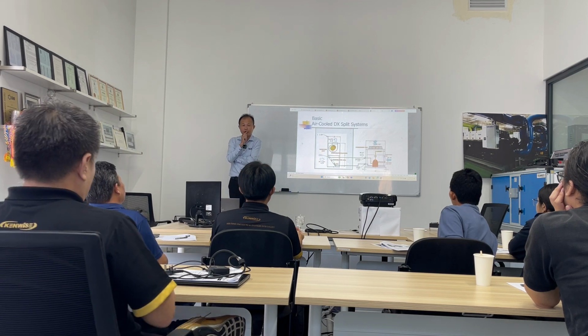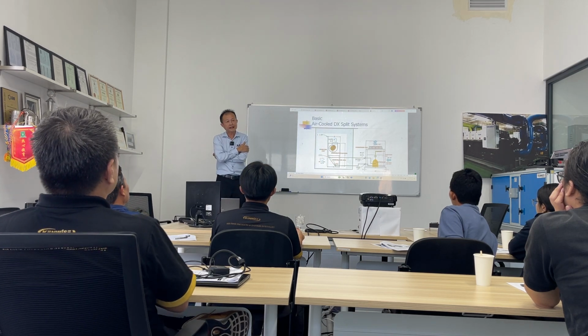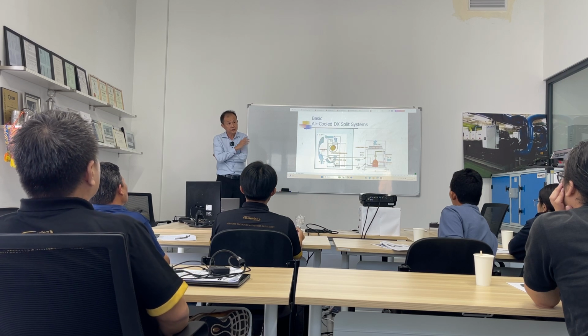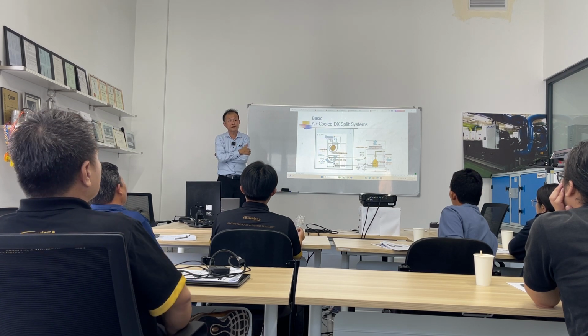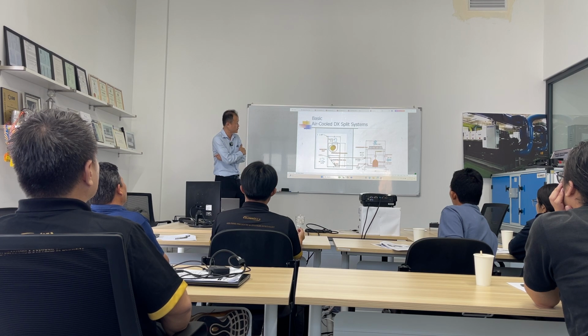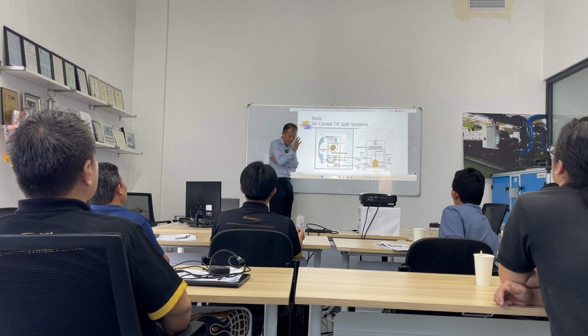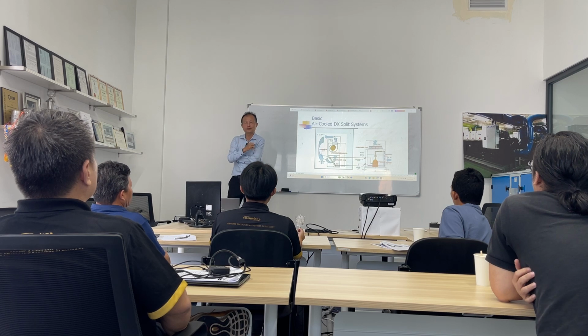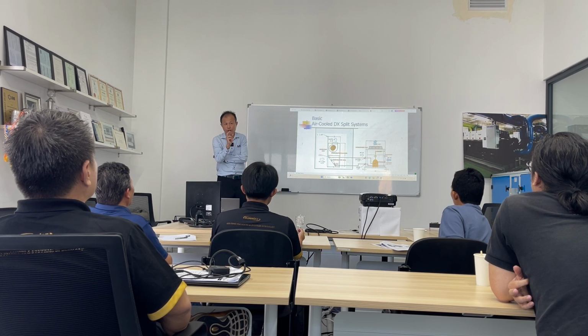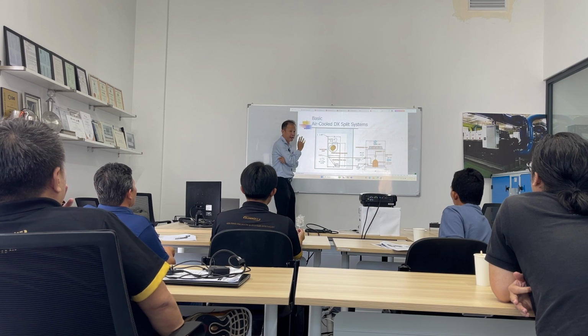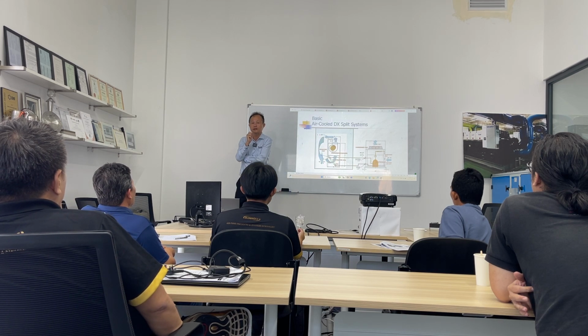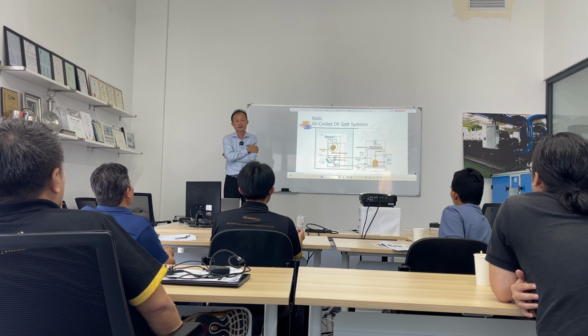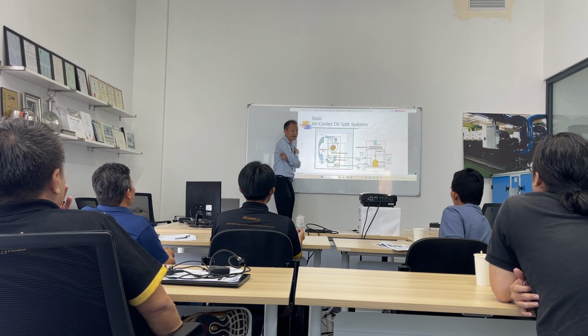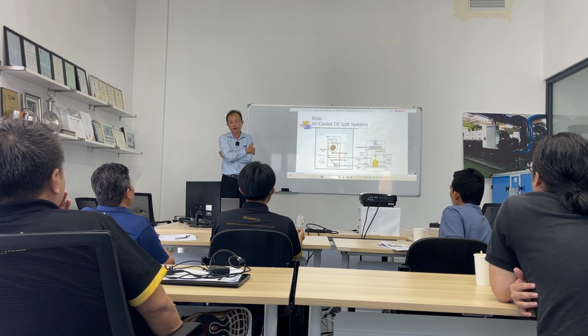When you select aircon equipment in the supplier catalogs, supposedly they have very many technical data. You need to actually use that to select equipment. One of it is the air on-coil temperature through the cooling coil. So what is the likely air on-coil temperature from this one that you can see?